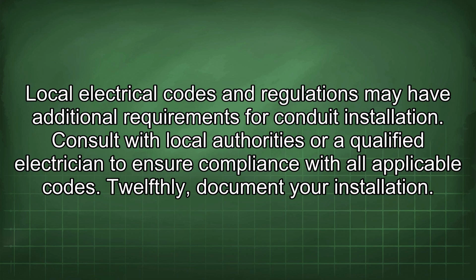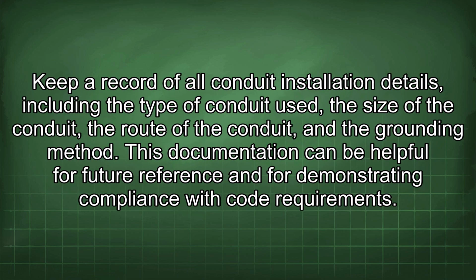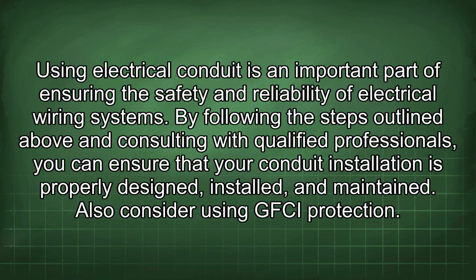12thly, document your installation. Keep a record of all conduit installation details, including the type of conduit used, the size of the conduit, the route of the conduit, and the grounding method. This documentation can be helpful for future reference and for demonstrating compliance with code requirements. Using electrical conduit is an important part of ensuring the safety and reliability of electrical wiring systems. By following the steps outlined above and consulting with qualified professionals, you can ensure that your conduit installation is properly designed, installed, and maintained. Also consider using GFCI protection.